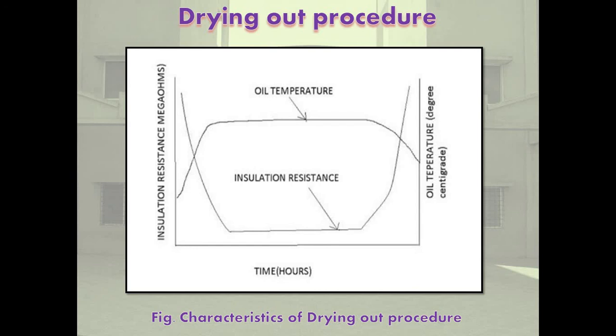During the drying out period, which extends from a few hours to several days, the following measurements are taken every one or two hours: insulation resistance value of 60 second and 15 second megger reading, alternatively 10 minute and 1 minute reading, winding temperature, oil temperature top, oil temperature bottom, and time from the beginning of the drying out. The initial resistance values are measured between each winding and earth and also between different windings.